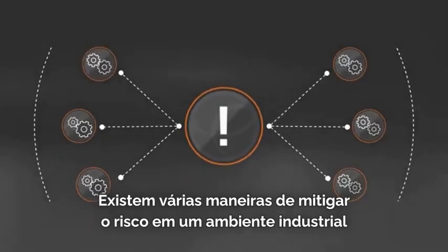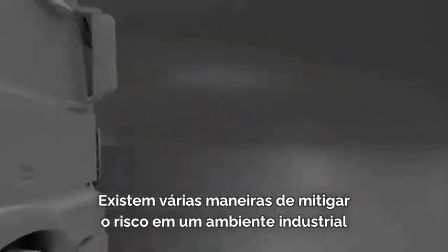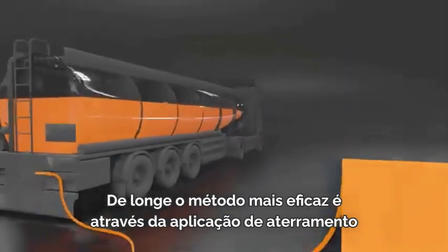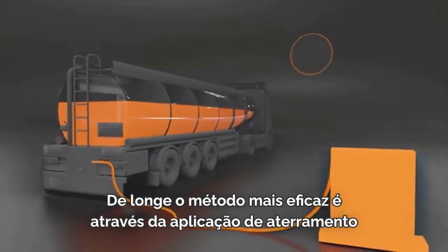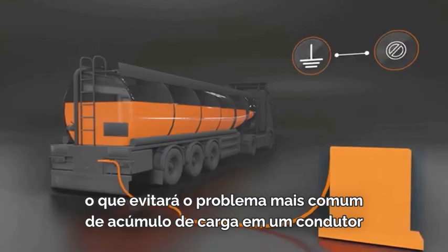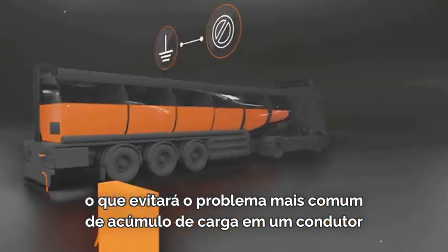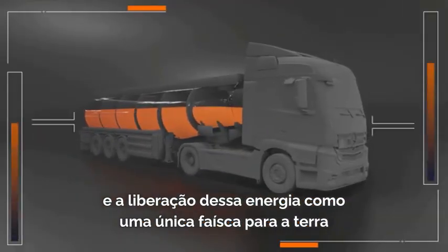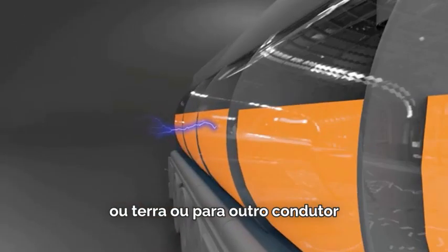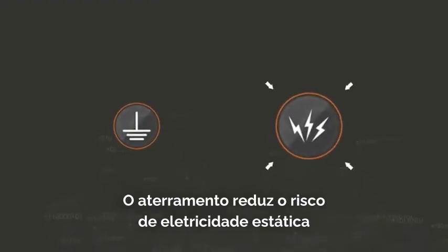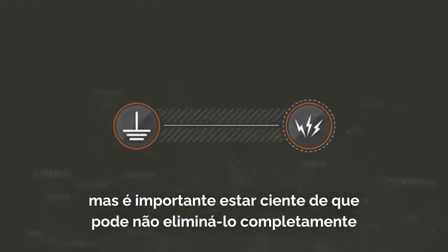There are various ways to mitigate the risk. In an industrial environment, by far the most effective method is through the application of earthing, which will prevent the most common problem, accumulation of charge on a conductor, and the release of that energy as a single spark to earth or ground or to another conductor. Earthing reduces the static electricity hazard, but it's important to be aware that it may not eliminate it completely.